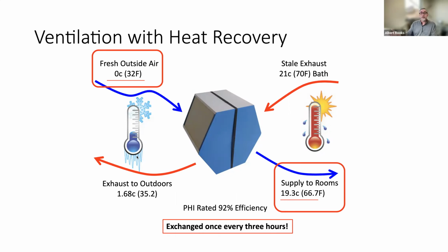So essentially all we're going to do is bring in fresh air at a rate of 50 CFM or 100 CFM, a number. And at the same time, we're going to bring conditioned air in from the exhaust points, kitchens and baths typically, run them by each other and transfer the heat. And in some of the buildings that I work in, we can save up to 92% of the heat energy and not send it outside the building. And when we modeled that in some of the buildings that we really get a chance to drill down and look at the model, we can actually make the equivalent of 2 inches of thermal insulation around the entire building. That heat recovery is worth 2 inches of insulation at R4 per inch. So it's almost worth a stripe of R8 all the way around the building, which is really pretty good.